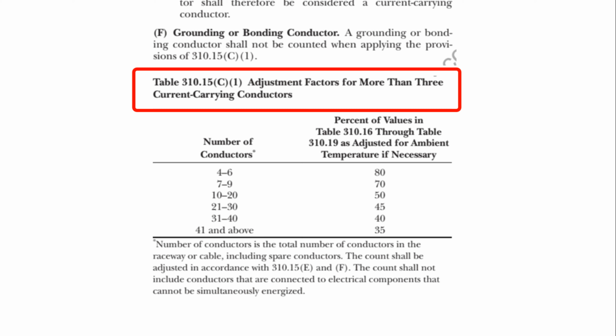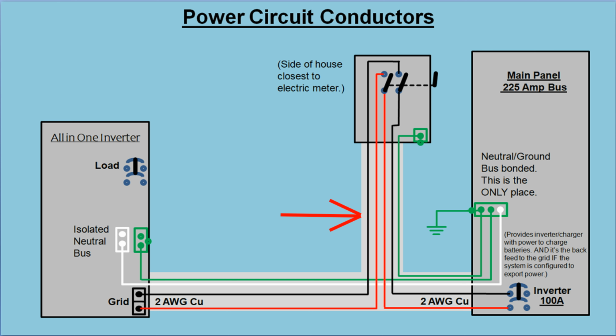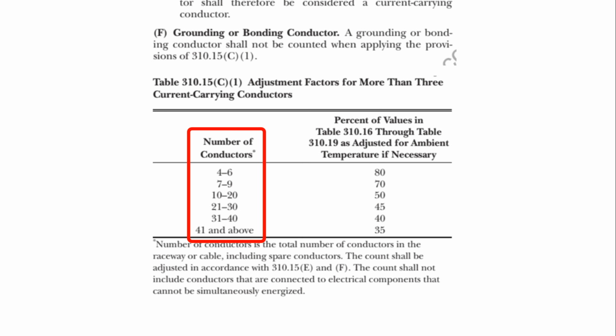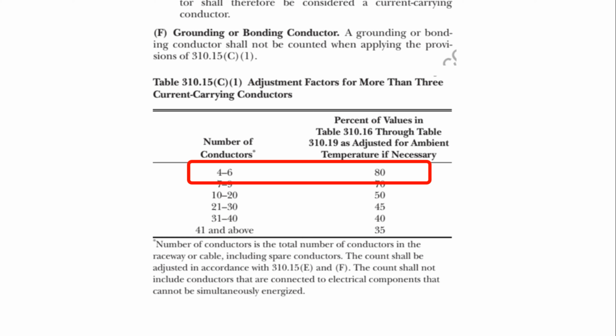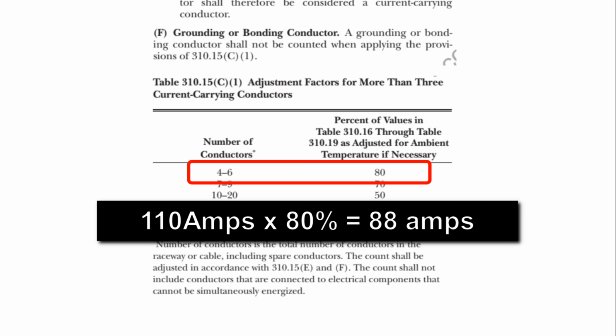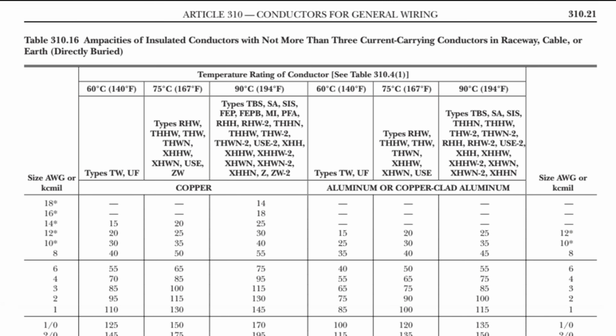We finally arrived at the meat and potatoes of 310.15, table 310.15c1, adjustment factors for more than 3 current-carrying conductors. Recall that I have 4 current-carrying conductors in this conduit. Based on the number of conductors, I'll need to apply an 80% limit on the temperature-corrected ampacity of these circuit conductors. 88 amps isn't 100 amps, so we now know that number 3 copper conductors aren't going to work in this circuit. We need to go back to the ampacity tables and select a different conductor size. The next size larger is number 2 AWG. And we can start our derating adjustments with 130 amps.